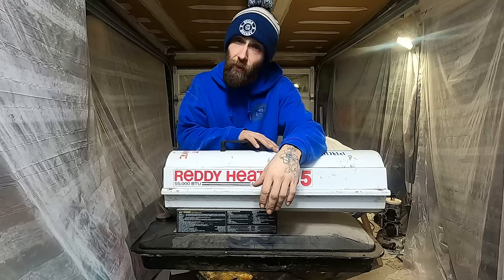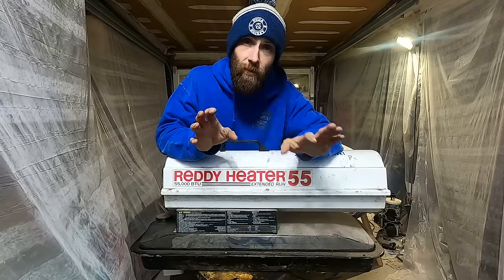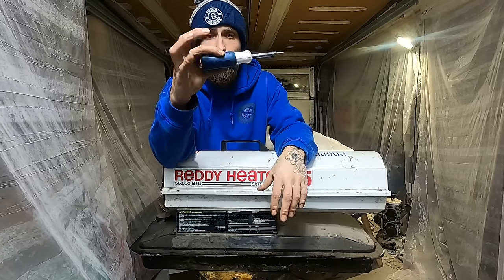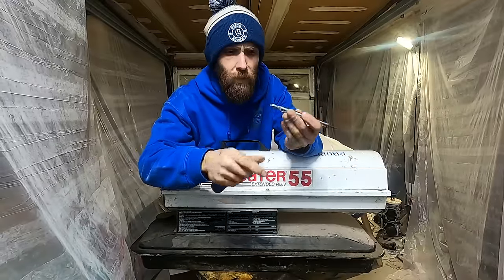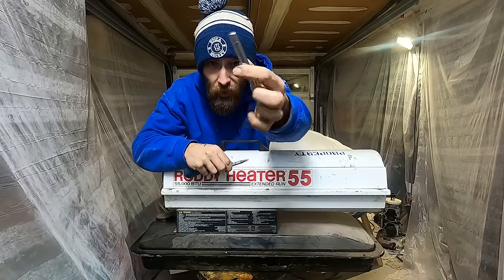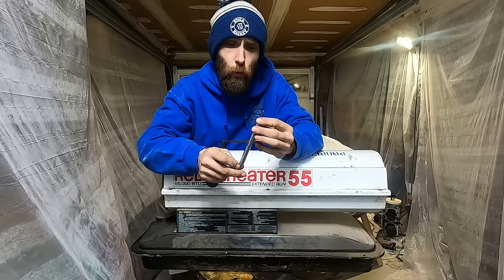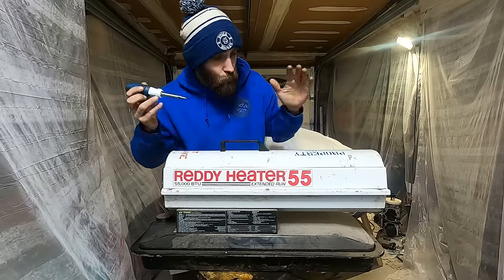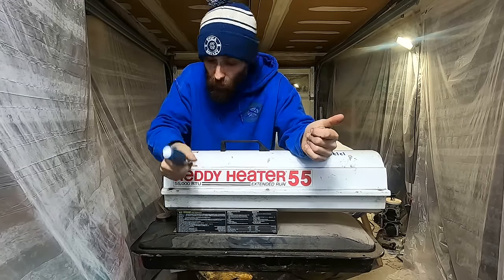What we're going to do today is go through the definitive list of how to service, maintain, and inspect every single component in one of these jet heaters so you can get them running. These things to me are like snowblowers — old world technology that hasn't been touched. You can still fix this entire thing with one of these: a six-in-one screwdriver. You've got a big Phillips, big flat, small Phillips, small flat — that's four — plus a quarter-inch hex and a 5/16ths hex. On these Reddy heaters, they're all made by about one company and everybody else slaps their name on it.